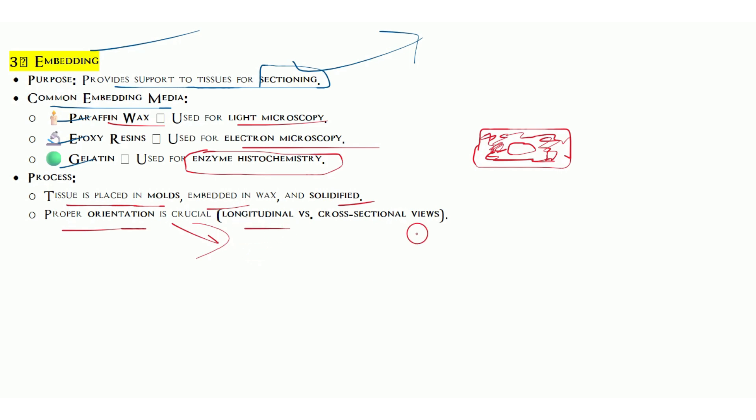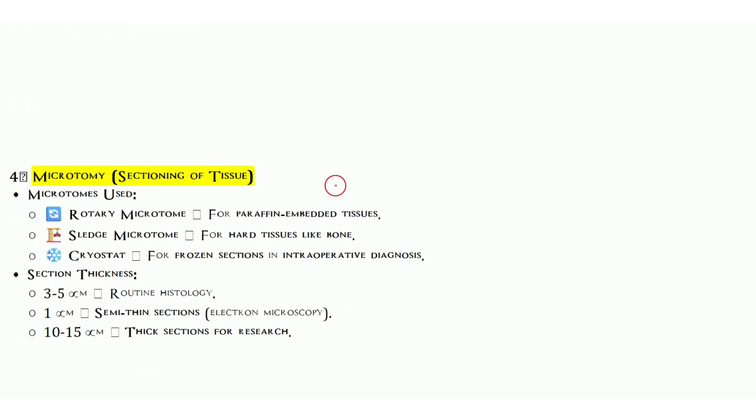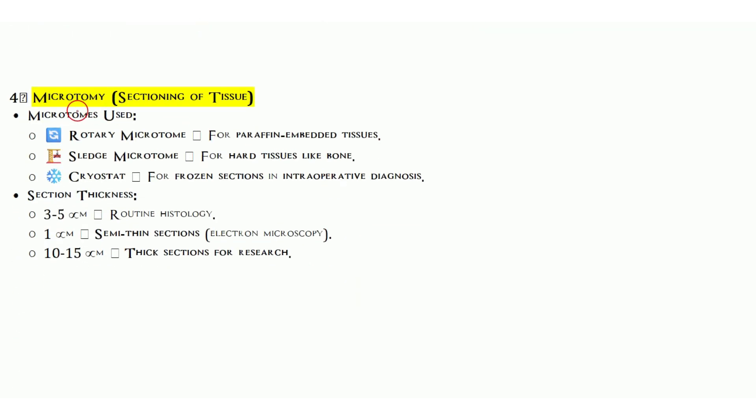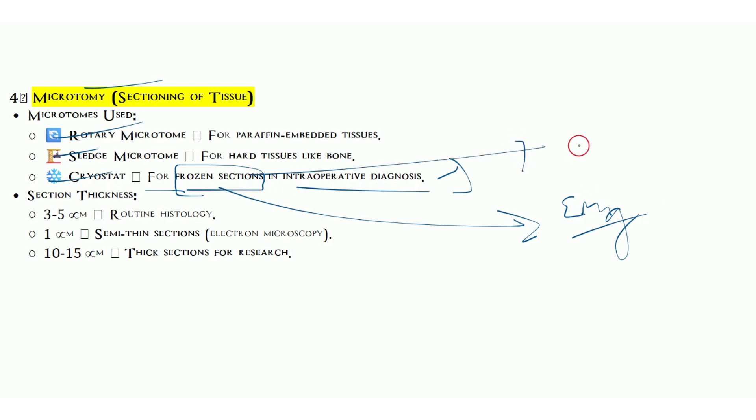Embedding wax solidifies with proper orientation. Orientation is very important in case of skin or some other tissues. We have to put them in longitudinal or cross-sectional view. Another section is microtomy. We have rotary microtome, sledge microtome, and cryostat for frozen sections. Cryostat is used for intraoperative diagnosis. Frozen sections are very important in case of emergency when the patient is in the emergency room or OT.